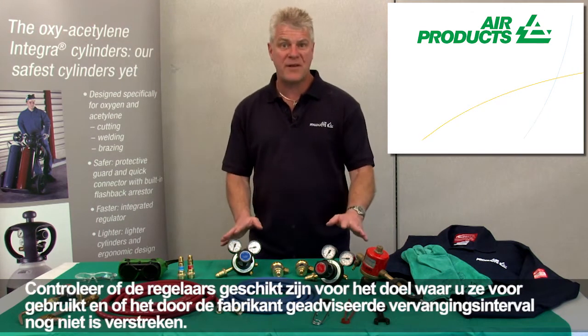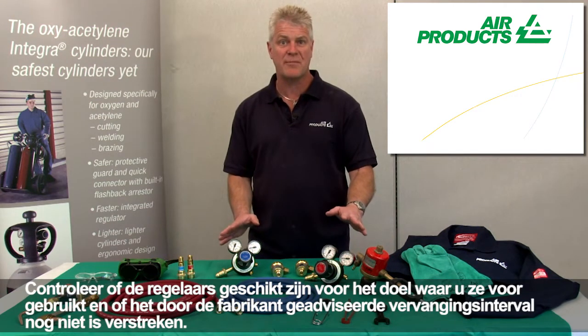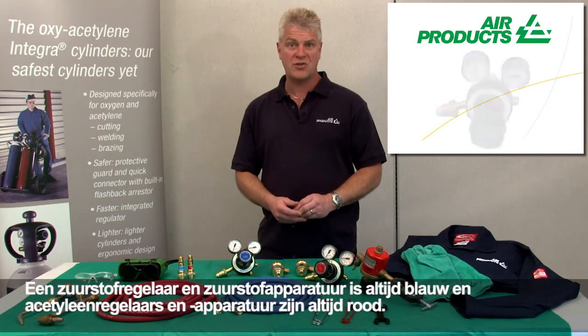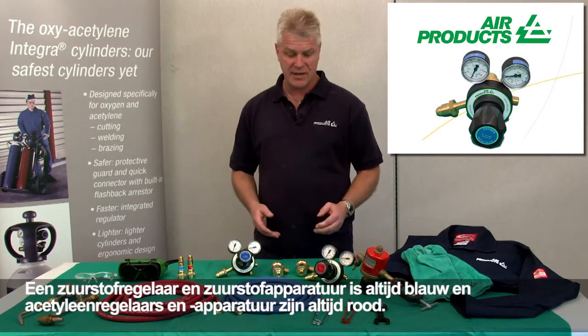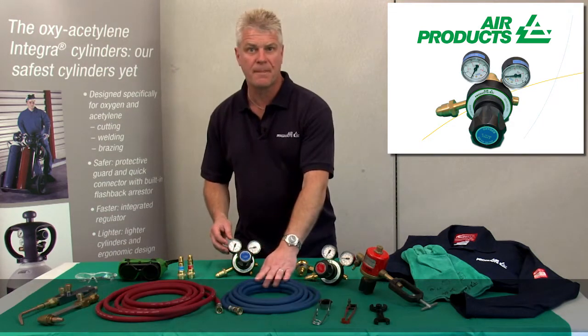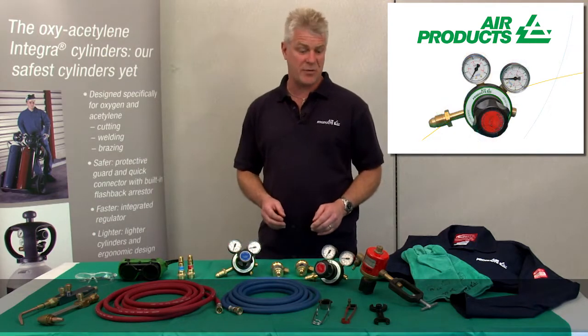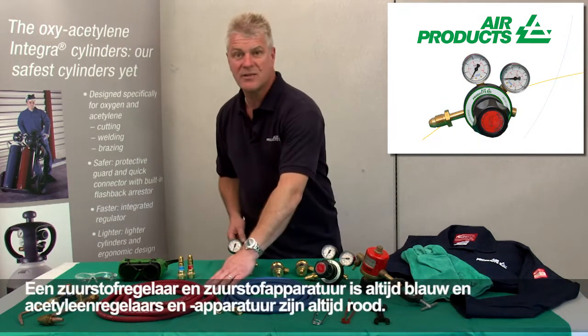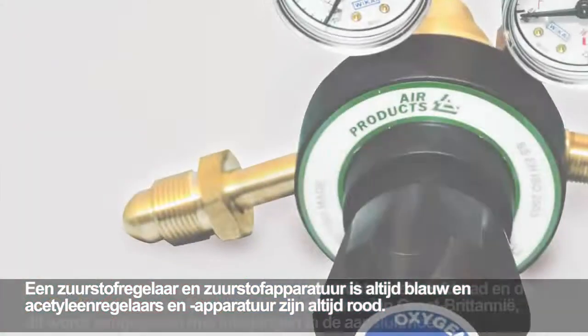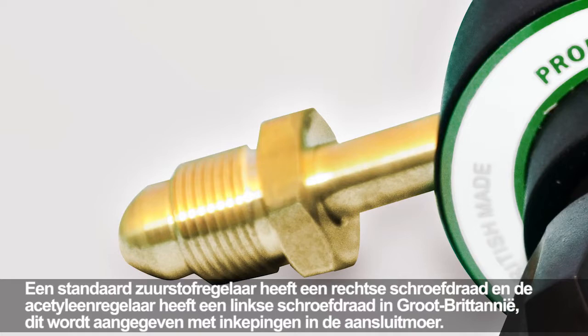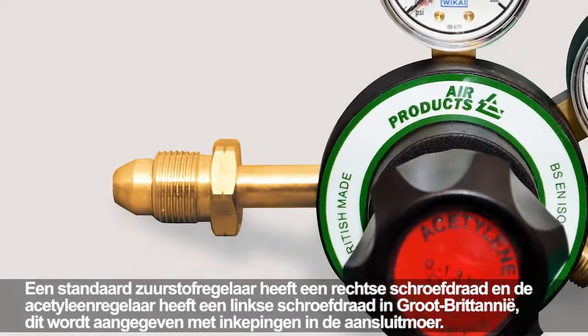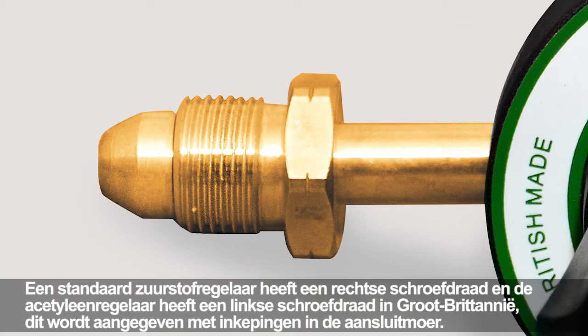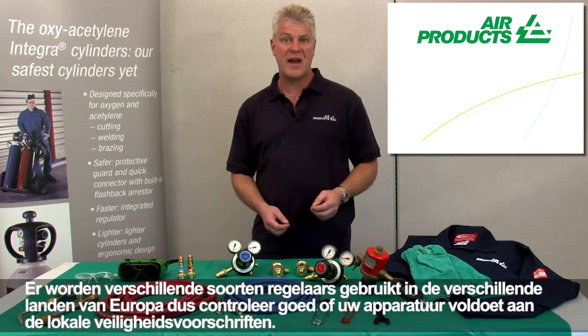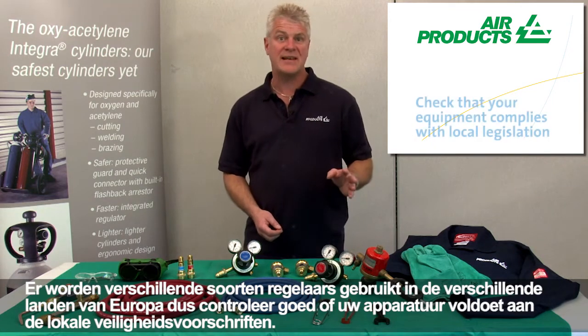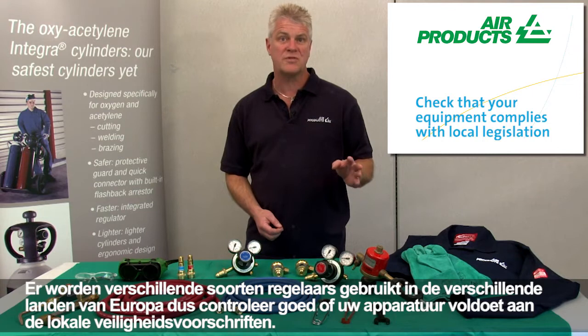Ensure that regulators are fit for purpose and within manufacturer's recommended replacement period. An oxygen regulator and equipment is always blue. Acetylene regulators and equipment is always red. A standard oxygen regulator has a right-hand thread and the acetylene regulator has a left-hand thread in the UK, identified by the notches in the connecting nut. Regulator types vary between European countries, so please ensure your equipment complies with local safety legislation.